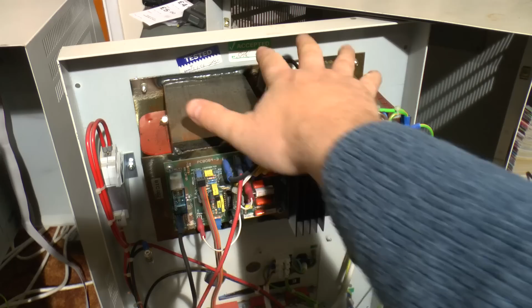This large transformer isn't just a transformer. We've got the mains transformer over here, which has two taps. You can run it at 240 or 220 volts. You change the neutral tap over here, and this large choke on the black and the white connections, which goes down to here. And as you can see, they are actually welded on a single metal sheet, rather than two separate transformers.